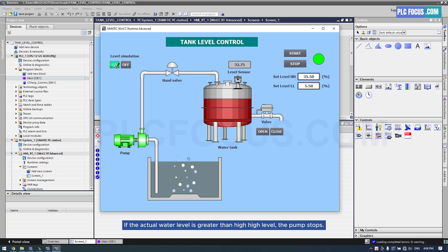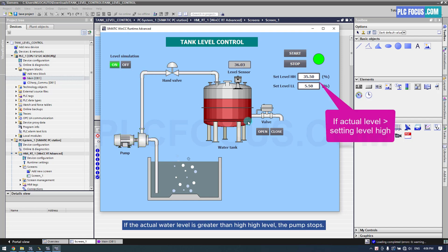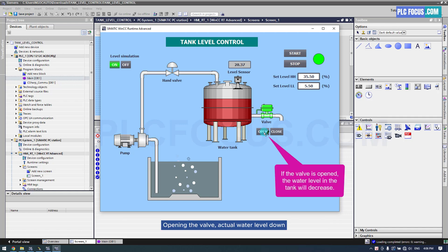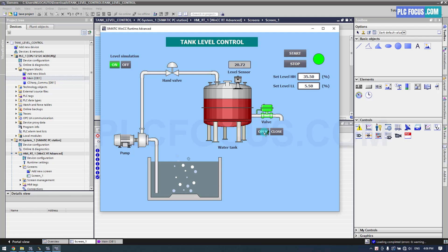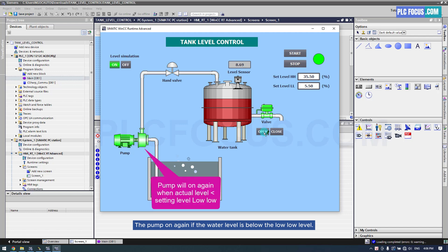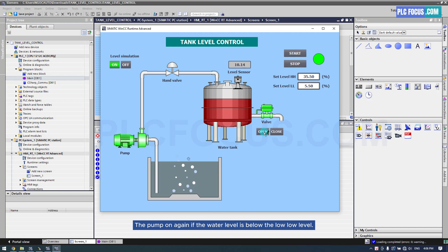If the actual water level is greater than the high-high level, the pump stops. Opening the valve causes the actual water level to go down. The pump turns on again if the water level is below the low-low level.